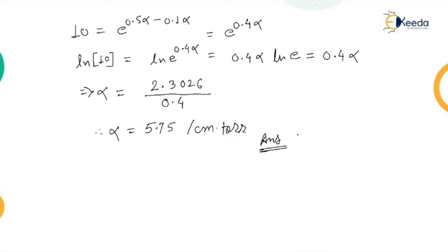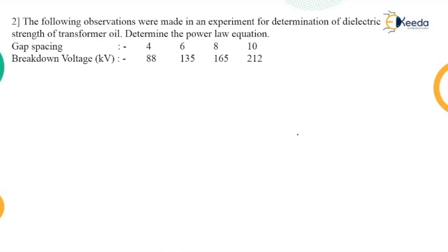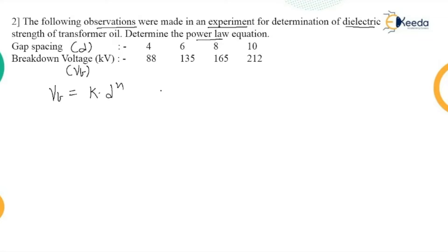Now let us consider the second numerical. This is an experiment to determine the dielectric strength of oil. Given gap spacing d in centimeters and breakdown voltage in kilovolts, we have to find the power law equation VB = K × d^n, where K and n are unknown.